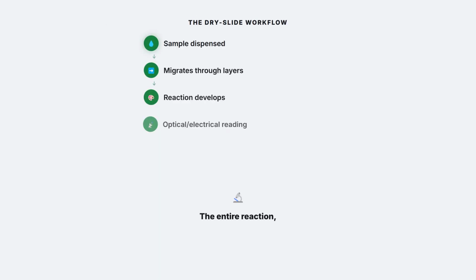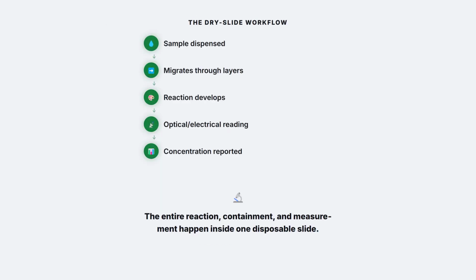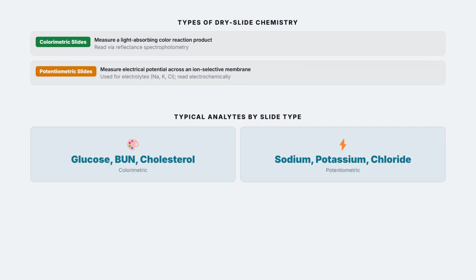The basic workflow, end-to-end, is deliberately simple. A metered sample drop is dispensed onto the slide. The sample migrates and reacts through the layered structure. A color or potential change develops. An optical or electrochemical reader measures that change. The instrument's software converts the reading into a reported concentration, the entire reaction, containment, and measurement happening inside one disposable element. Dry slide chemistry isn't one single technology.